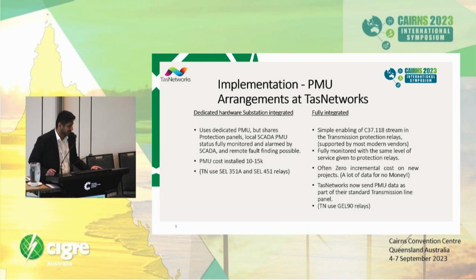Standalone units have more processor speed because they are dedicated ones, but it's kind of an expensive deal for a utility. We have to spend 10 to 15 grand to implement it, while the other option is to use the relays which come with a PMU card, which is just a comms card that activates C37.118. So we have moved in that direction: if we are commissioning a new bay, or something new is coming up in a project, we activate the PMU stream in these relays to have more visibility of synchrophasor data.